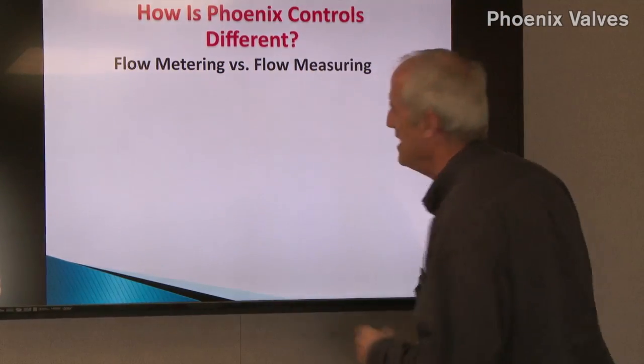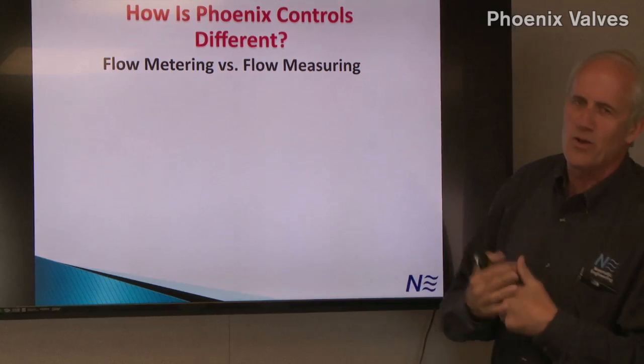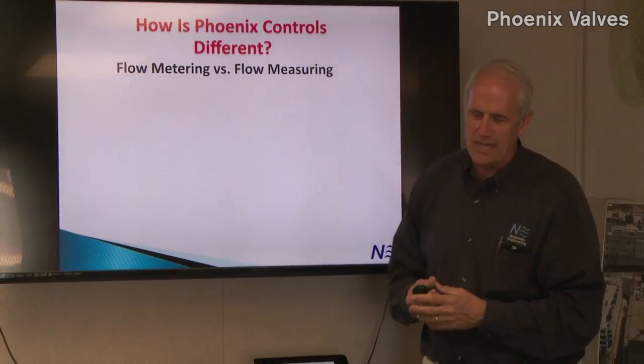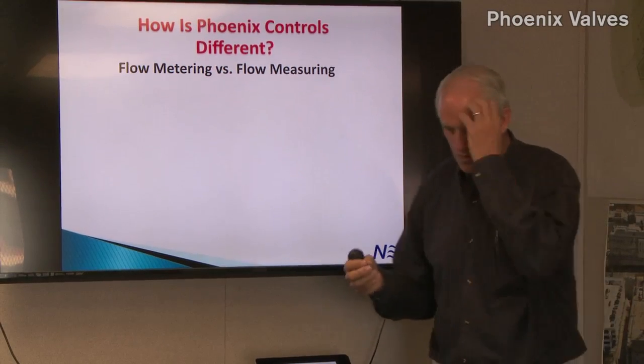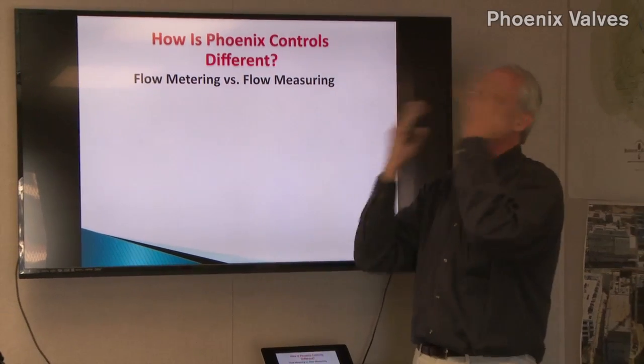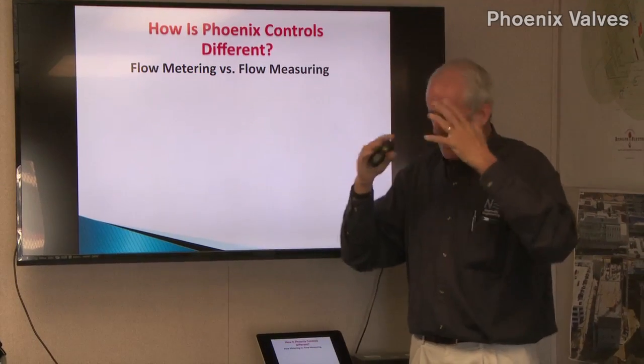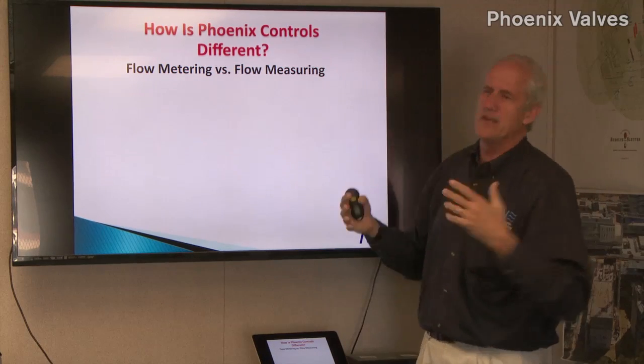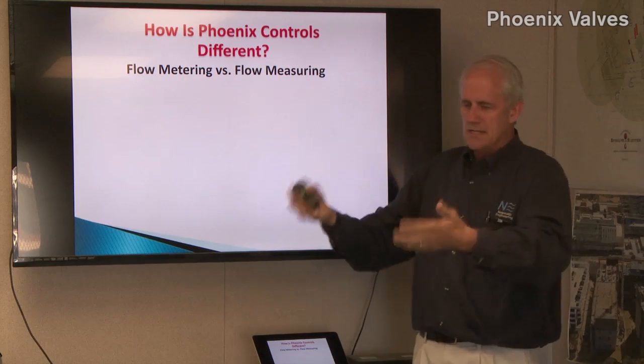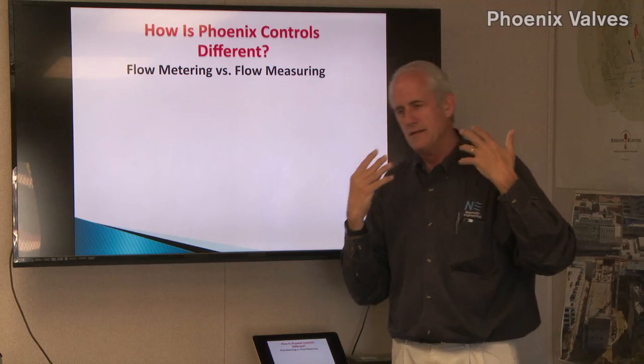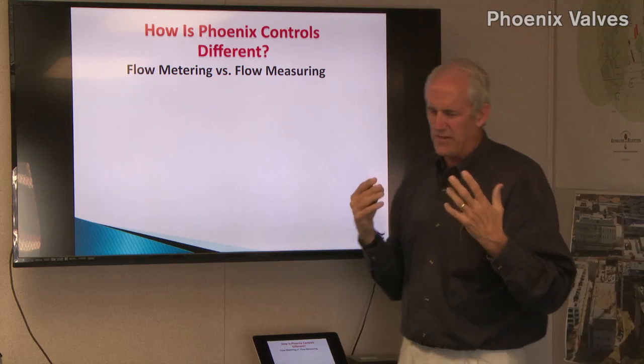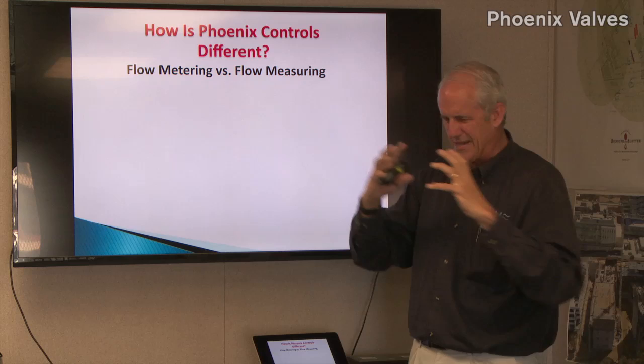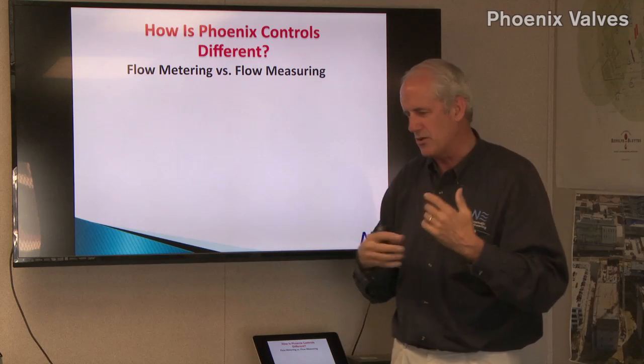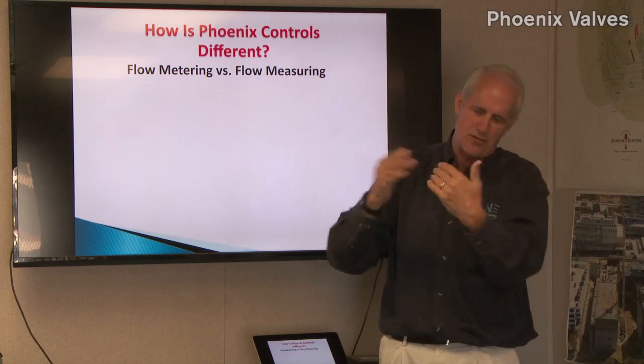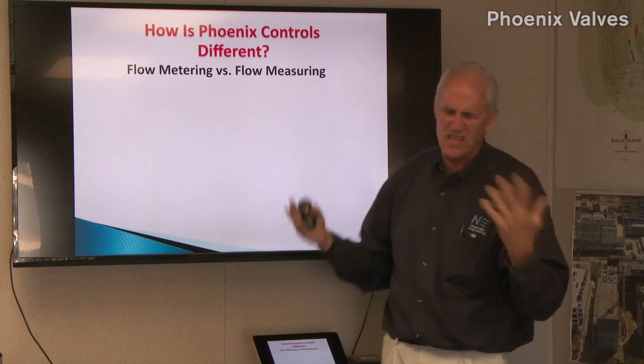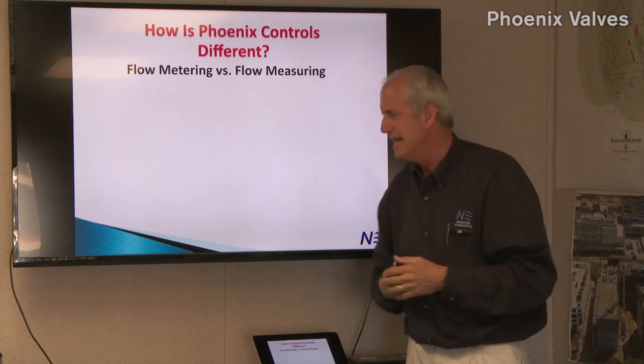Okay. So what Phoenix does, it controls airflow in a completely different way from the way everyone else does. With a VAV box, it's measuring air pressure, and it says, okay, I think that's 800 CFM or whatever it is. It measures the velocity pressure of the air. You can't really measure the velocity pressure directly because the static pressure is built into that number. So it measures total pressure, static pressure, takes a differential and gives you velocity pressure. So with a VAV box, you're kind of measuring the flow.